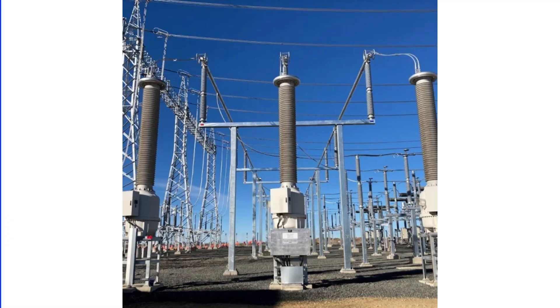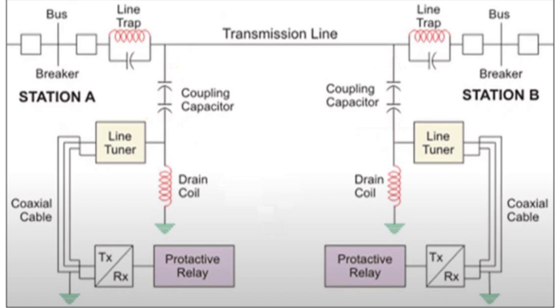The Coupling Capacitor, or Capacitive Voltage Transformer, connects the carrier equipment to the transmission line. It offers low impedance to high-frequency carrier signals while providing high impedance to the 50 Hz power frequency. This allows the carrier frequency signal to safely enter the PLCC equipment. To make the circuit purely resistive, an inductor is added in series with the capacitor, forming a resonant circuit that reduces reactive power.